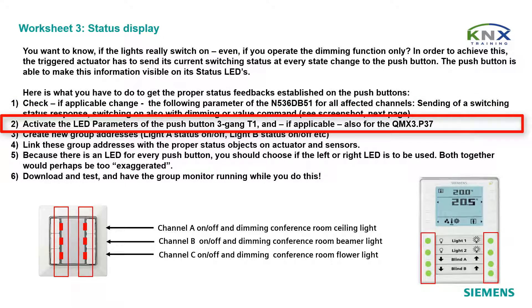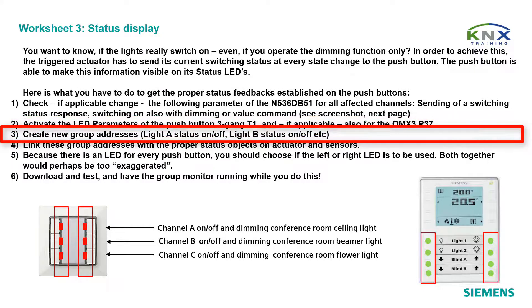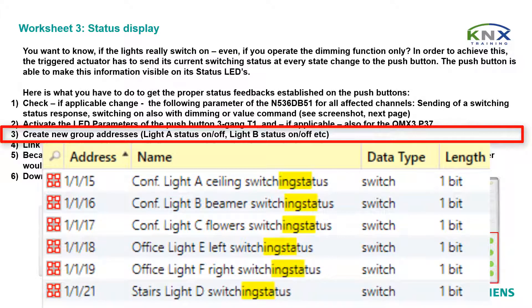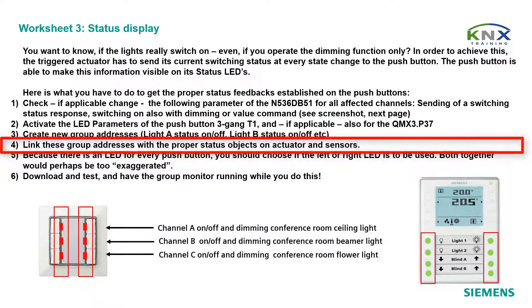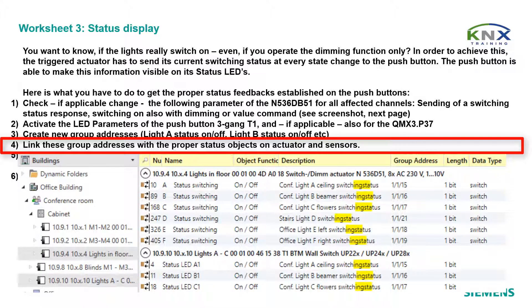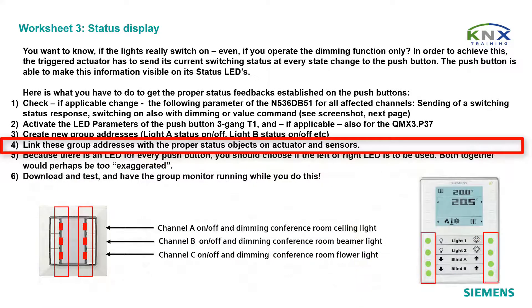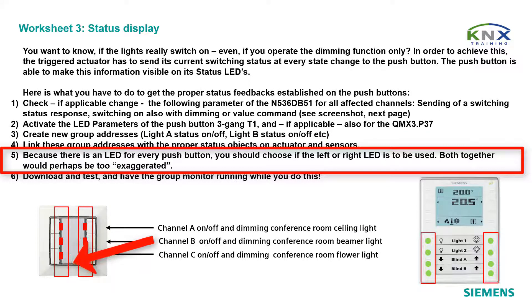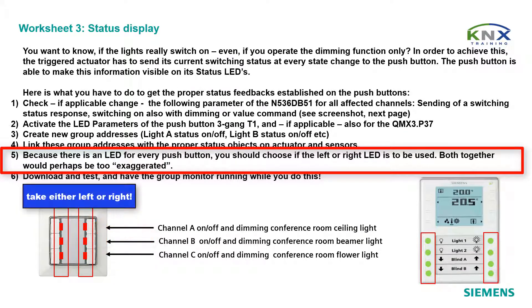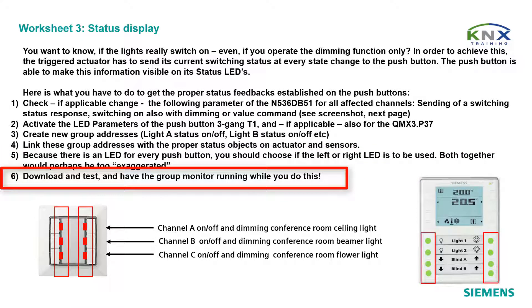Activate the LED parameters of the push button 3-Gang T1 and, if applicable, also for the QMX3 P37. Create new group addresses: Light A status on/off, Light B status on/off, etc. Link these group addresses with the proper status objects on actuator and sensors. Because there is an LED for every push button, choose whether the left or right LED row is to be used — both together would perhaps be too much. Finally, download and test with the group monitor running while you do this.